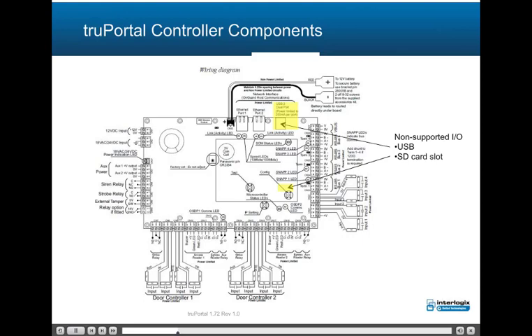The I-O board, the larger of the two boards, contains the power supply and all field wiring connections. Each reader port can accommodate a reader that utilizes Wiegand Data 1/Data 0, LED control, and buzzer control. Twelve supervised inputs, excluding tamper and power monitor, are provided for door sense, reader tamper, request to exit (RTE), and auxiliary input. Four auxiliary supervised inputs are also included.